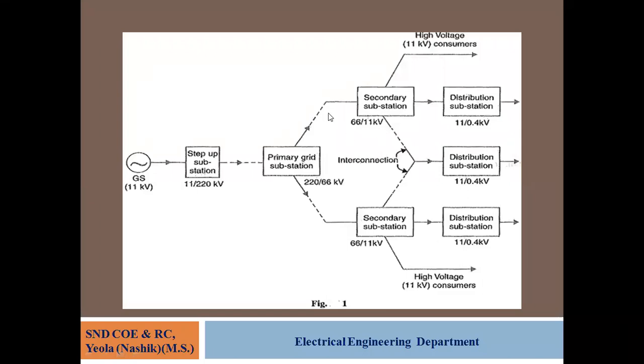This works in two-way direction, and the lines interconnecting these secondary substations are called the interconnection of these two substations. This means if one substation fails due to some reason, power can be supplied from another path to the distribution system - from primary to secondary, secondary to distribution substation - so that the substation continues getting power from the source.